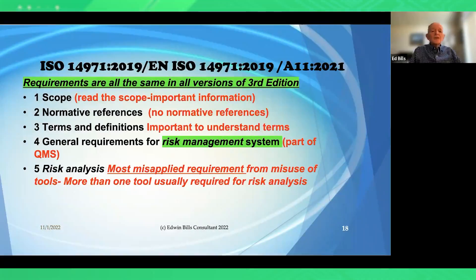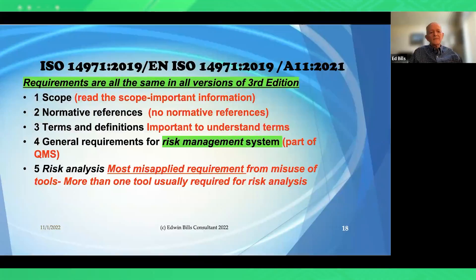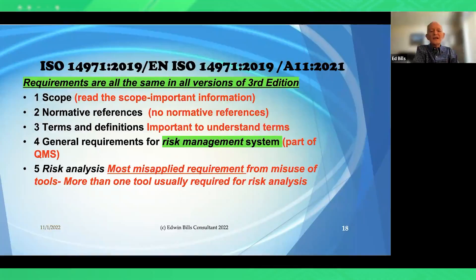Make sure you understand the terms and definitions — things like FMEA use a different set. FMEA's definition of risk is the probability of occurrence of a failure and the severity of the effect of the failure, not the probability of occurrence of harm and the severity of harm as defined in ISO 14971. Clause four covers the general requirements for a risk management system — it is part of a quality management system. The word 'system' is now specifically required for MDR and IVDR compliance, so understand what that means when an auditor comes in.